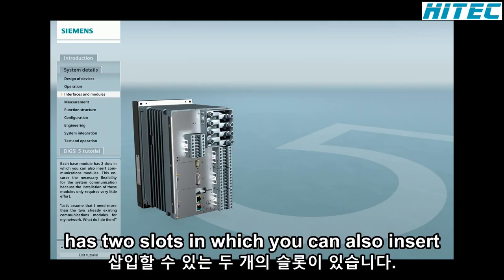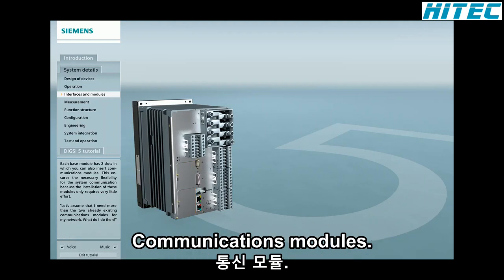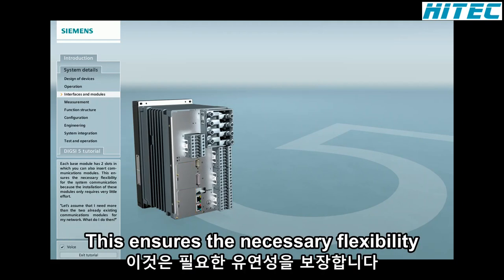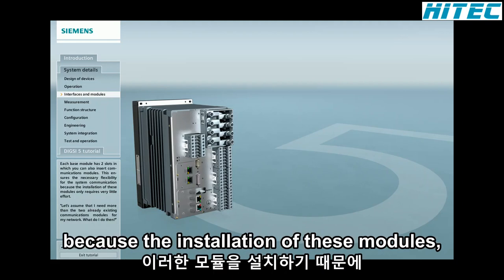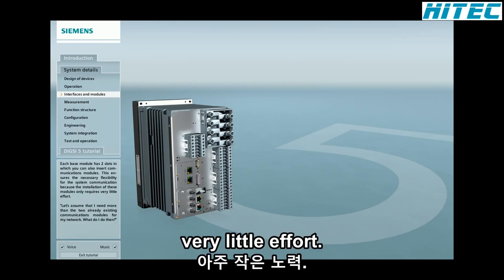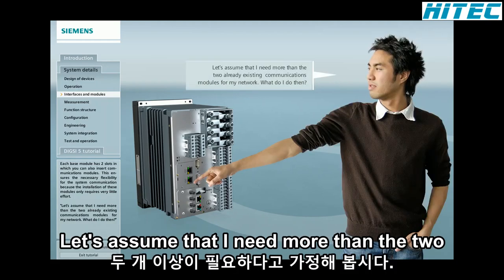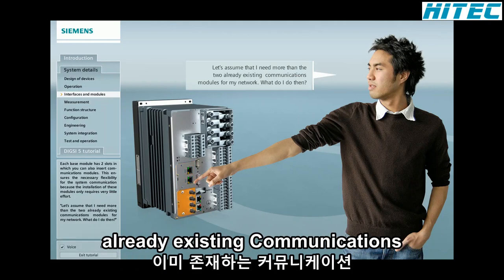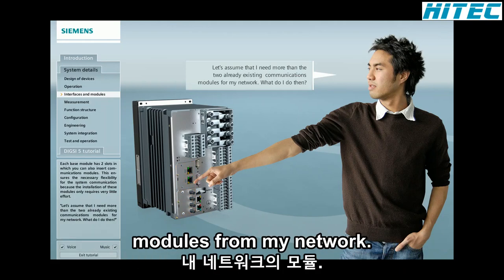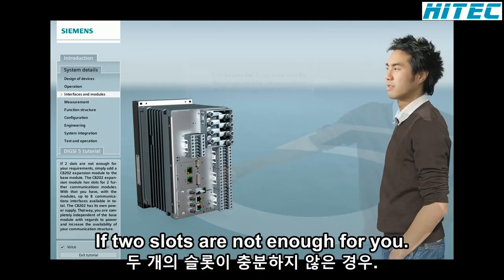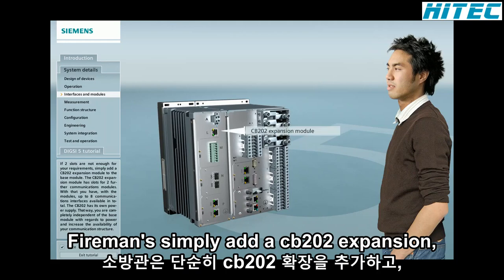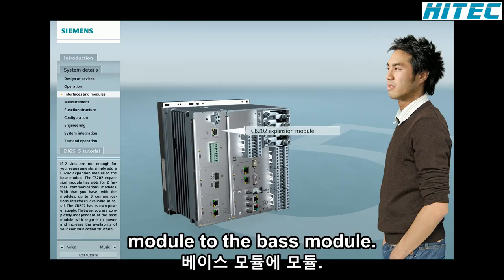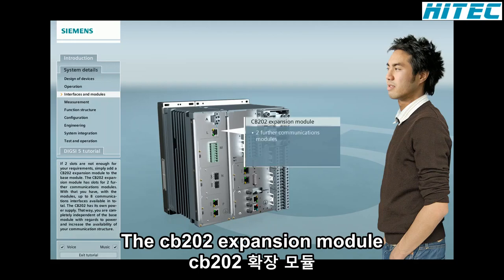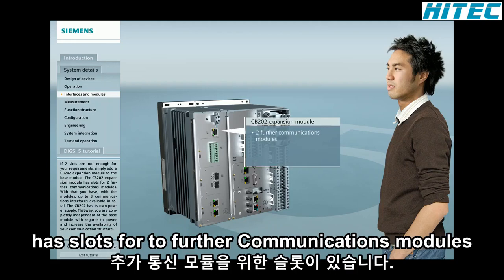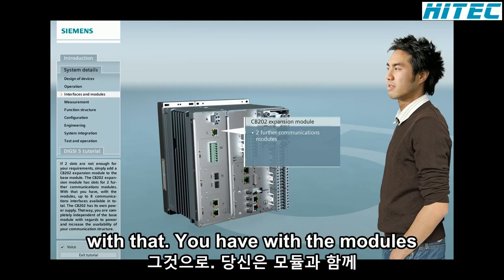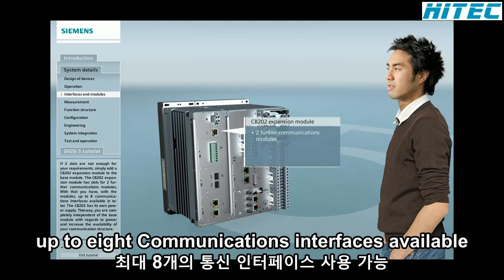Each base module has 2 slots in which you can also insert communications modules. This ensures the necessary flexibility for the system communication because the installation of these modules only requires very little effort. Let's assume that I need more than the 2 already existing communications modules for my network. What do I do then? If 2 slots are not enough for your requirements, simply add a CB202 expansion module to the base module. The CB202 expansion module has slots for 2 further communications modules. With that, you have, with the modules, up to 8 communications interfaces available in total.